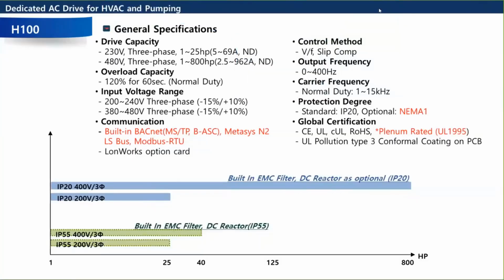And so we're going to start out with the most basic stuff here, and then we're going to work our way through all of the features and functions. First is the general specs, which is important to know because we're going to talk about some of the capacities. So the first question you should be asking when you're picking out a drive is, what motor are you connecting this to? 10 horse, 20 horse, 100 horse, 600 horse. And then, what's the voltage? Are you running 230, you're running 480, single phase, three phase?